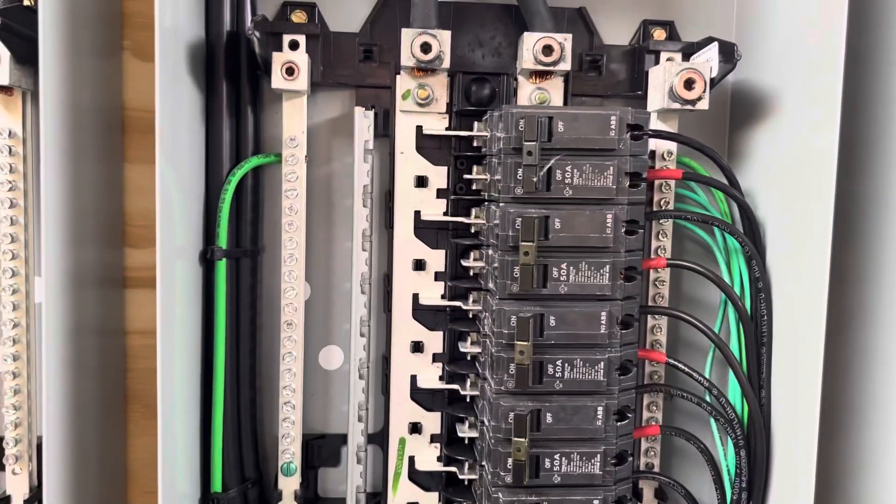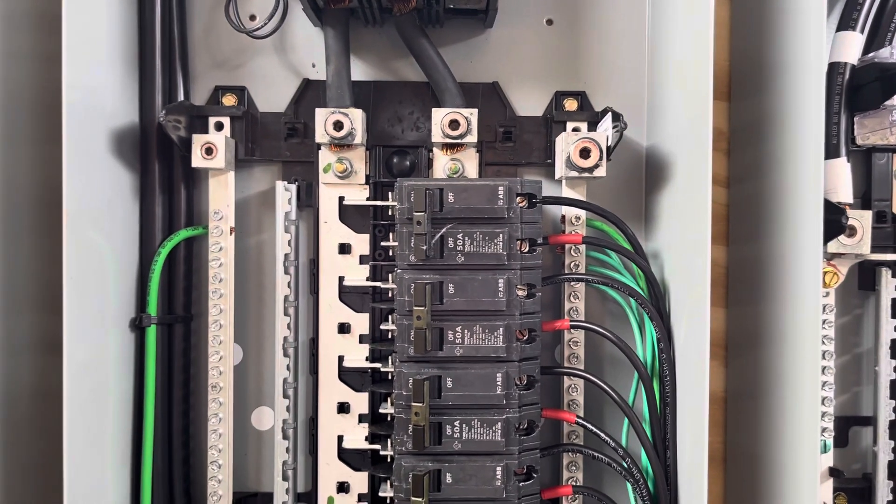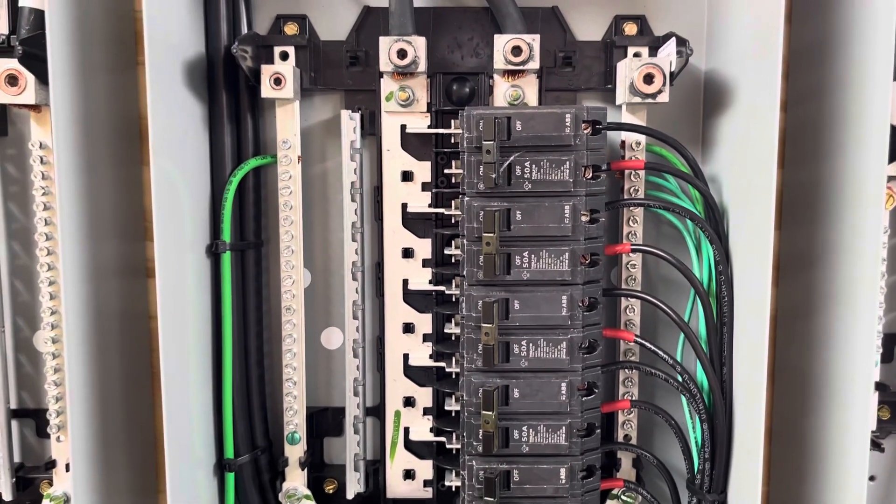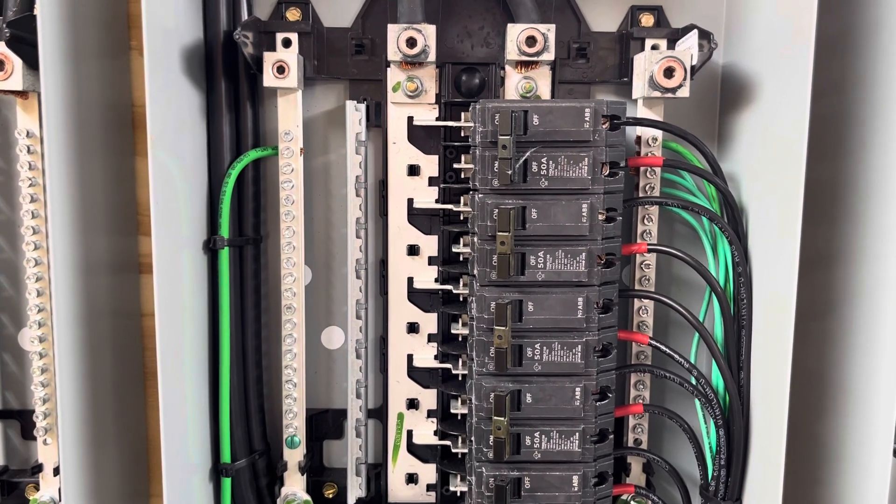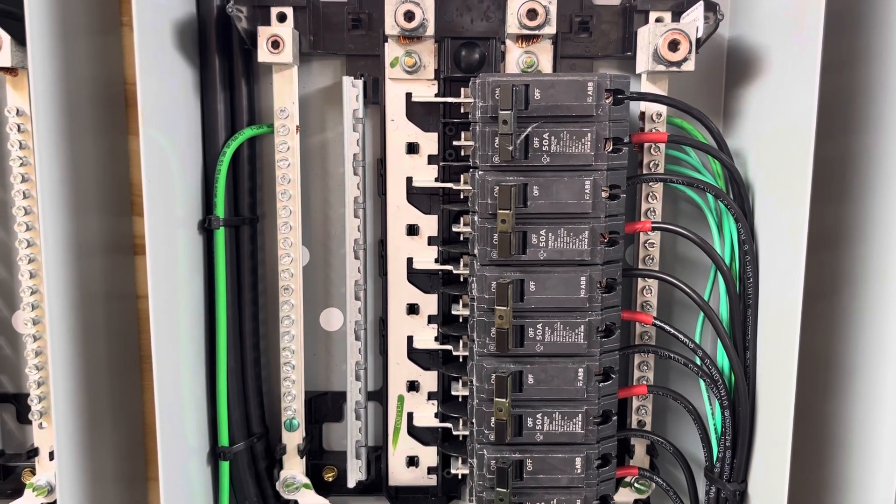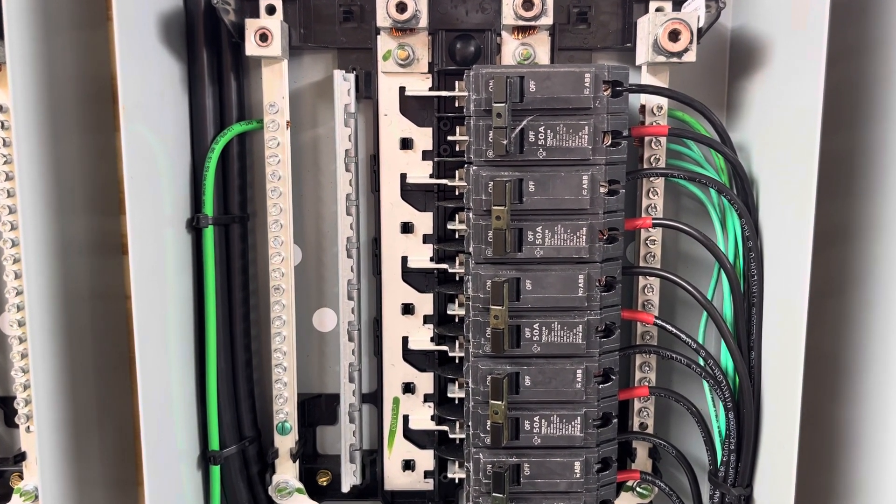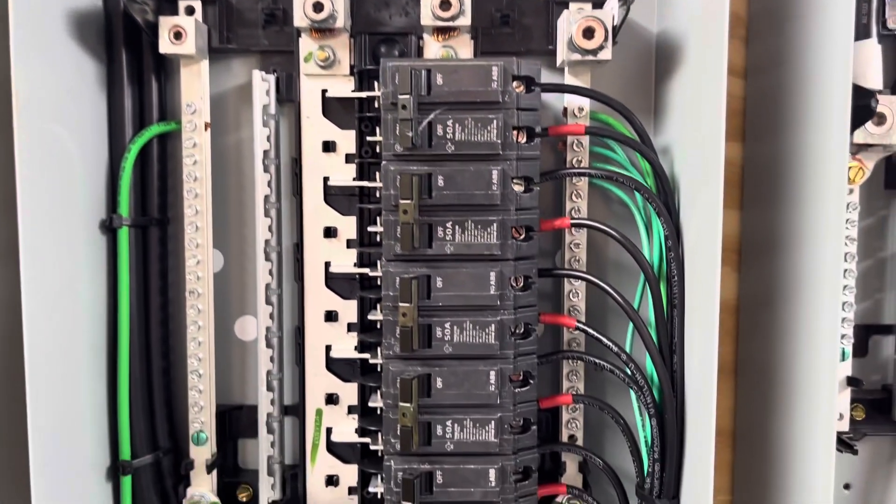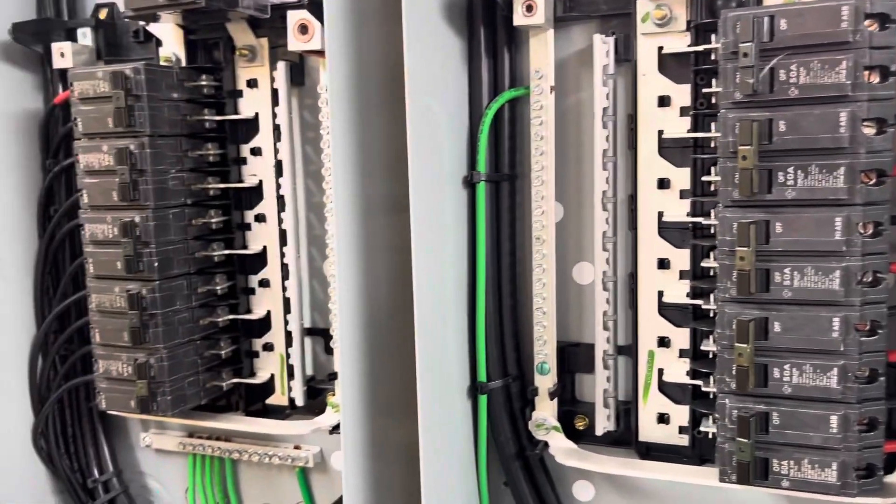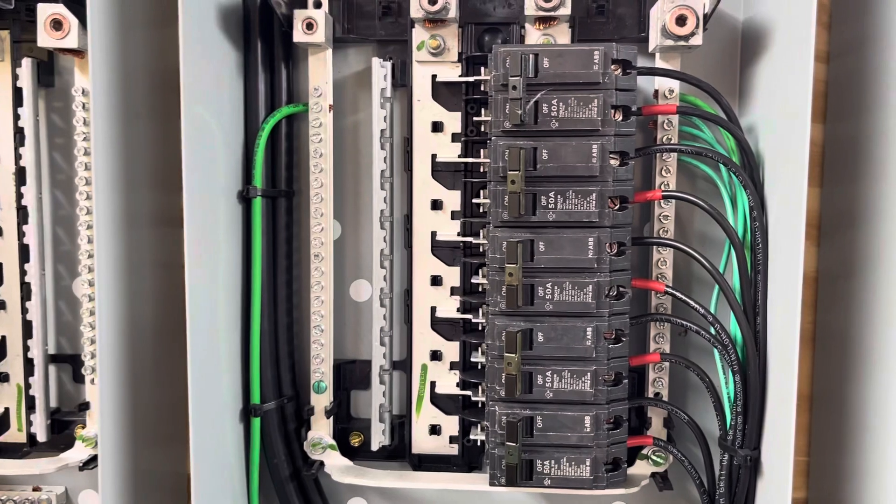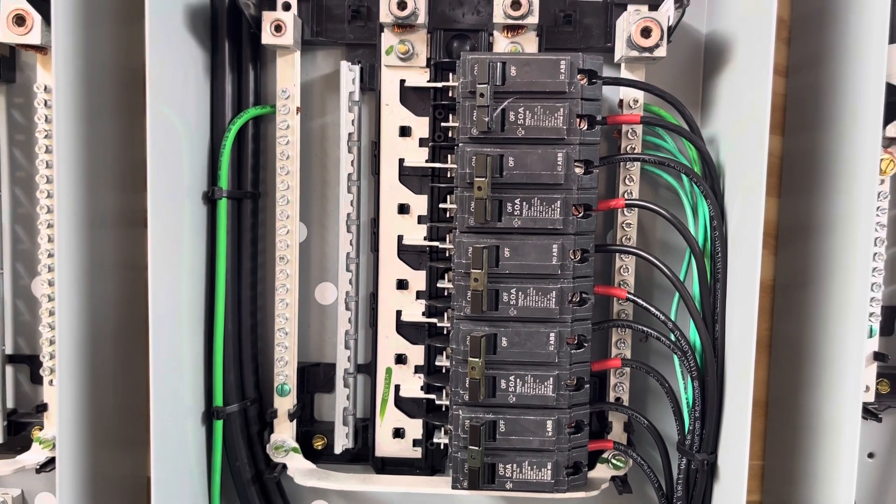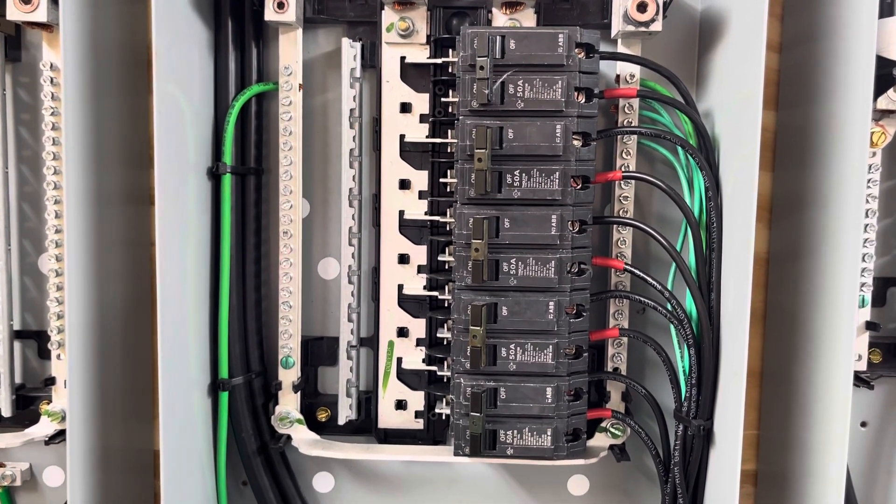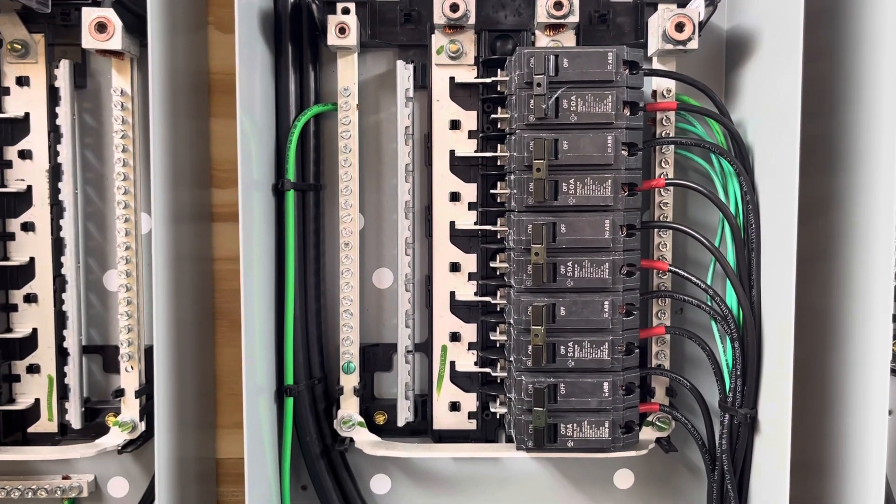Now, when it's in inverter mode, the grid does not pass directly through the inverter. Everything goes through the inversion process, and when it's going through the inversion process, whether it's the battery, whether it's the PV panel, or a blending of the utility and the PV panel, the inverter output is isolated from the utility input. And it has to be that way, otherwise you could back feed into the electrical grid, which is a big no-no.